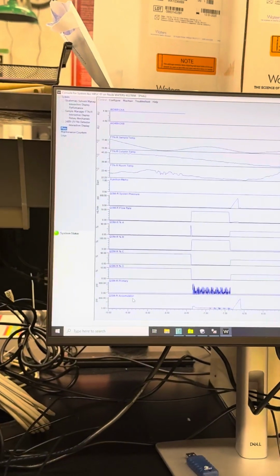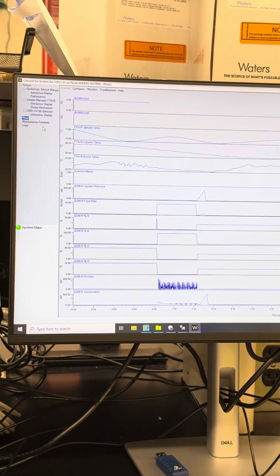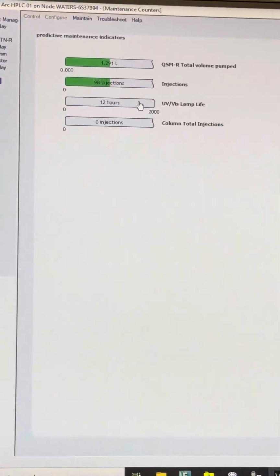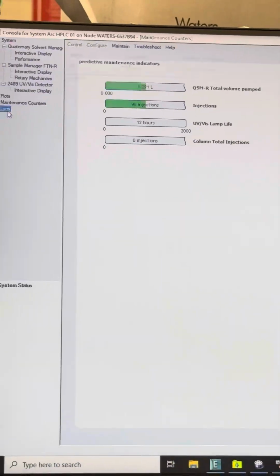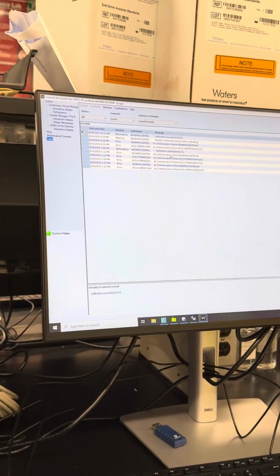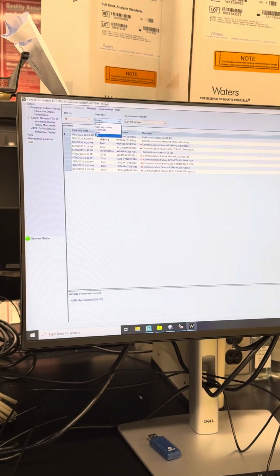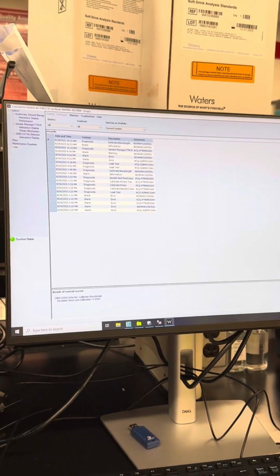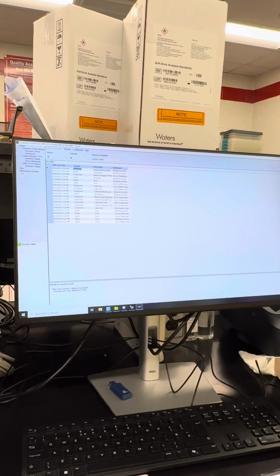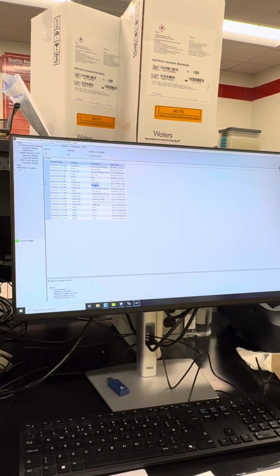You have your interactive display, as I said, your plots. This will give you all of your different plots on all of your different modules here. Maintenance counters, total amount pumped, injections, your lamp hours, column injections. Then your logs, if there's ever any errors, like here I had some communication errors when I was setting up. This is where they'll show. You also have diagnostics, user log entries, run, so you can kind of set those all. So as you can see, we ran our calibrate wavelength along with my other tests that I ran. So I ran a leak test, and it gives you everything there. So that is the console.